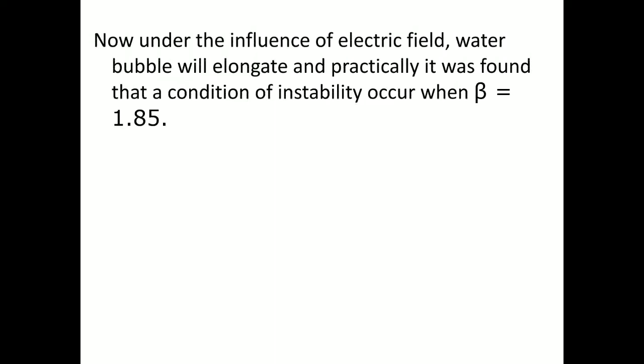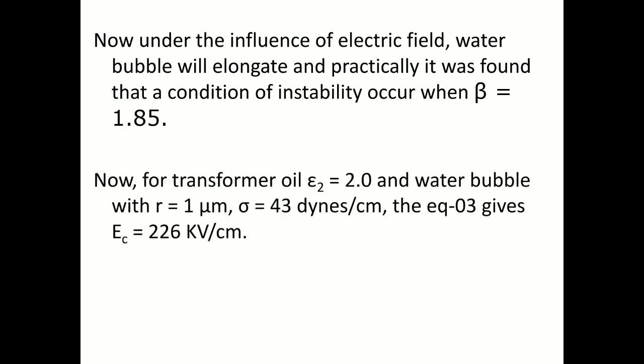Practically, it was found that under the influence of the electric field, when the value of beta is around 1.85, this leads to instability in the liquid dielectric medium. If we consider transformer oil as the operating medium — where epsilon 2 equals 2, water bubble radius is 1 micrometer, and sigma is 43 dyne per centimeter — and put all these parameters in equation number 3, the value of critical electric field strength comes out to be 226 kV per centimeter. This is the basic philosophy behind cavity breakdown mechanism in liquid dielectric media.